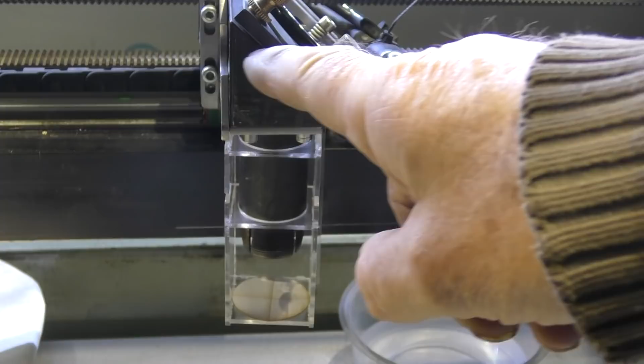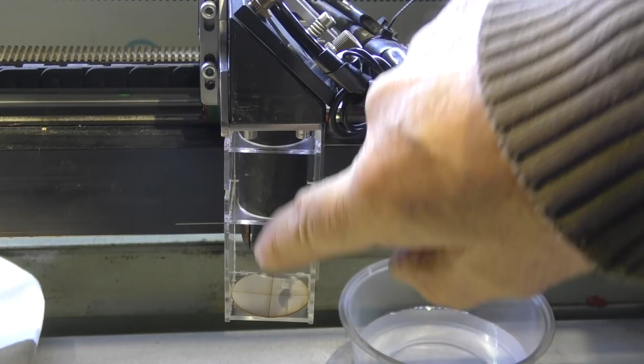We need to use one of these targets now in my special fixture here. And what we're going to do, we're going to put that in there like that. It just clips neatly in there. If we've got the beam coming in correctly here, hitting this mirror in the right place, it will go dead true down the centre of this axis here and hit the centre of my target. And that's what we're trying to do. We're trying to hit something that I call on that mirror the sweet spot. There is only one spot on that mirror where the beam will come and go perpendicular down through the central axis of the beam in both planes. It's not only got to be this plane, it's also got to be in this plane as well.